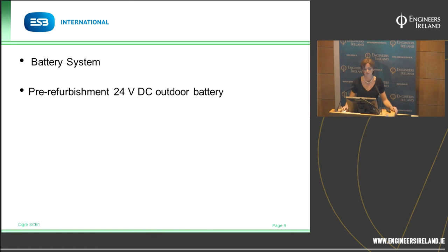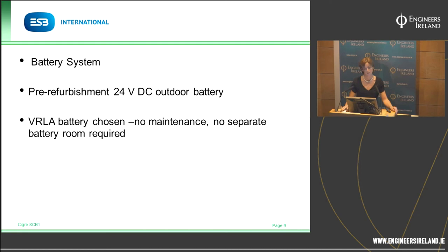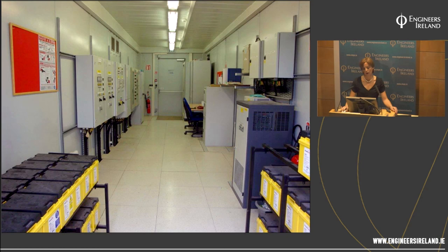So we chose a VRLA, valve regulated lead acid battery, which is sealed. It doesn't require any maintenance and it doesn't need a separate room. And you can see them there at the forefront of the picture, and that's the inside of a control room module.